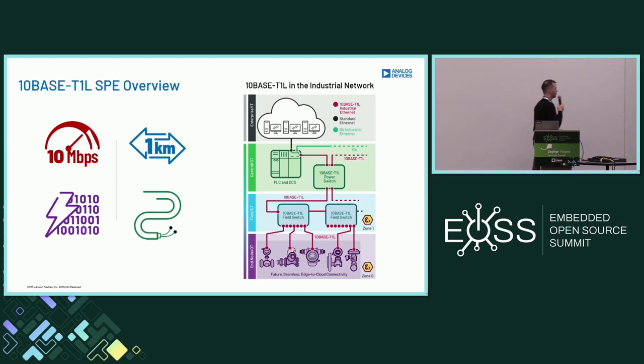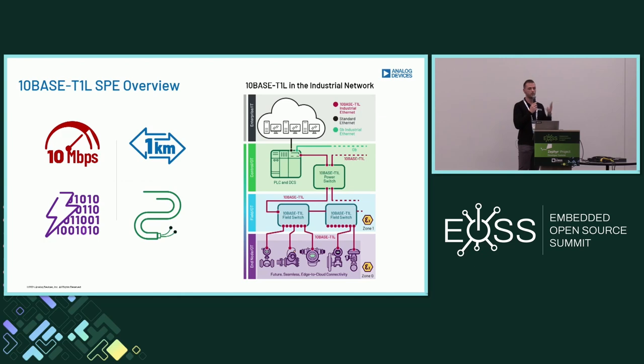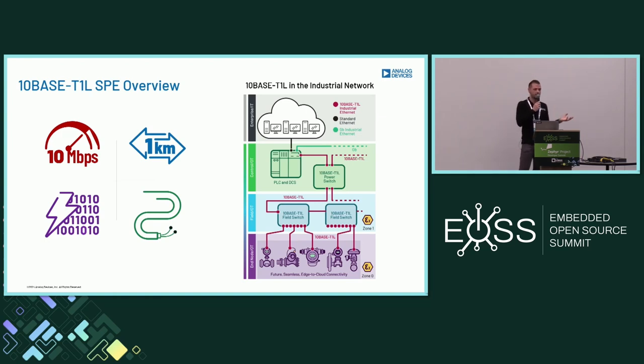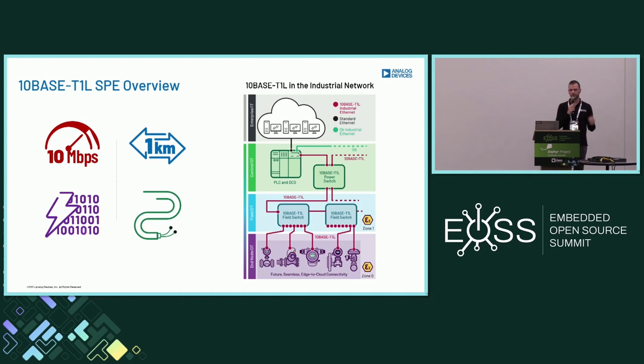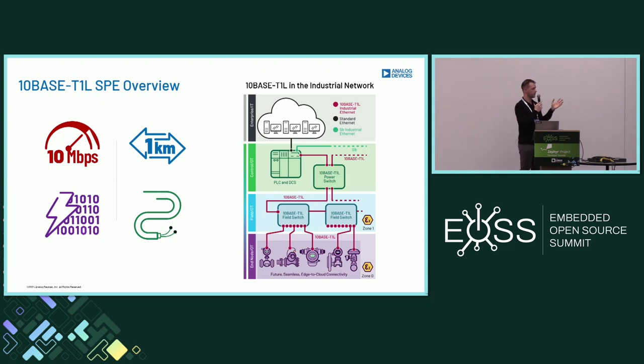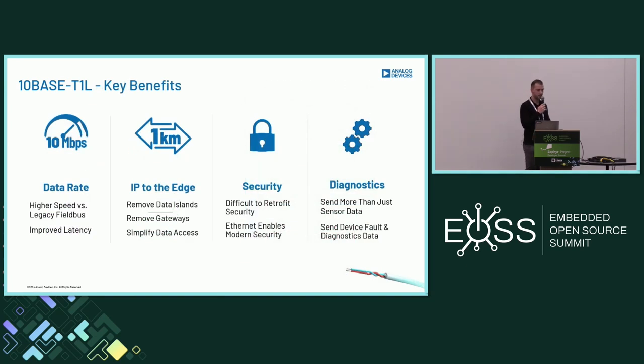What is 10BASE-T1L? You can summarize it in four key things: it's 10 megabit per second ethernet that operates over distances up to one kilometer, can carry power and data, all over a single twisted pair of cabling — just two wires. While your backbone, enterprise, cloud, and control levels remain with standard and gigabit industrial ethernet, 10BASE-T1L extends that physical layer to sensor and actuator type devices at the far reaches of industrial environments, resulting in a network that converges completely on ethernet with a seamless link from the edge to the cloud.